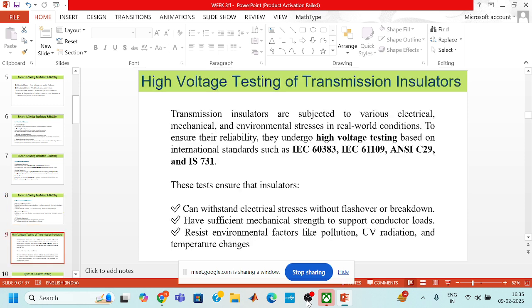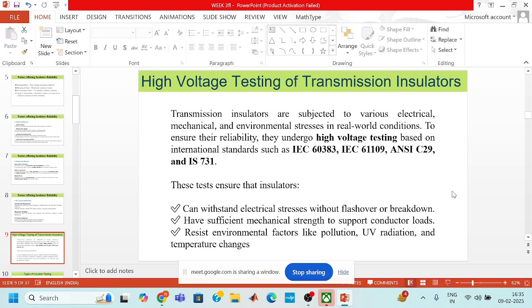Now there are some high voltage testing techniques for transmission insulators. As we know, transmission insulators are subjected to various electrical, mechanical, and environmental stresses in real world conditions. So these tests ensure their reliability, and they undergo high voltage testing based on international standards such as IEC 60383, IEC 61109, ANSI C29, and IS 731.